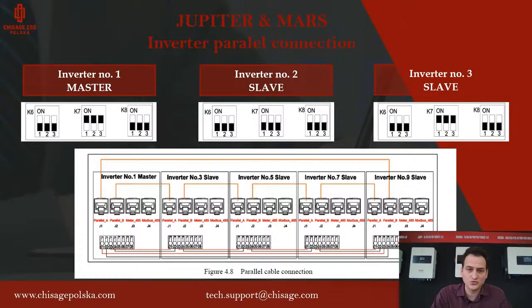Now I want to tell you a few things about parallel communication, about parallel connection for our inverters. So if we want to connect inverters in parallel, first thing we have to connect them with two cables. One is an Ethernet cable and the second one is a CAN parallel cable. We have to connect both. The inverter will only work correctly when we connect both.